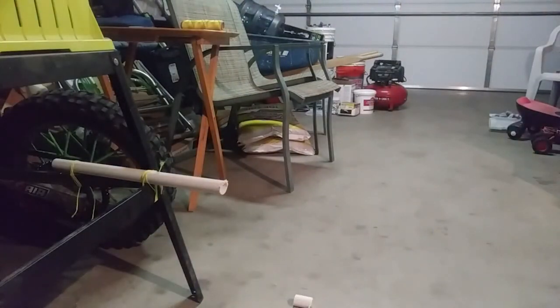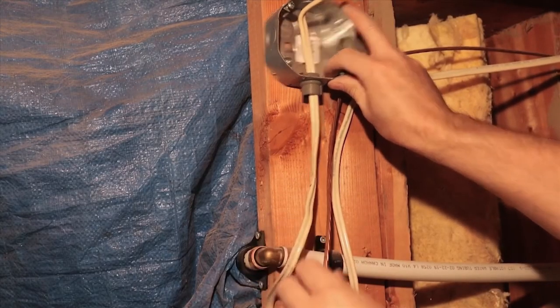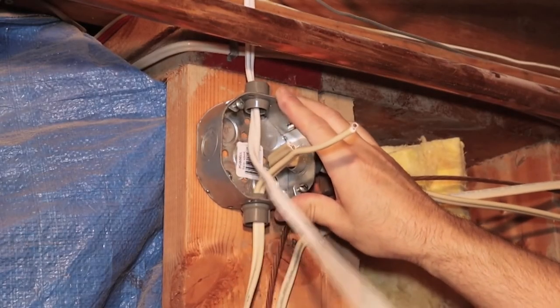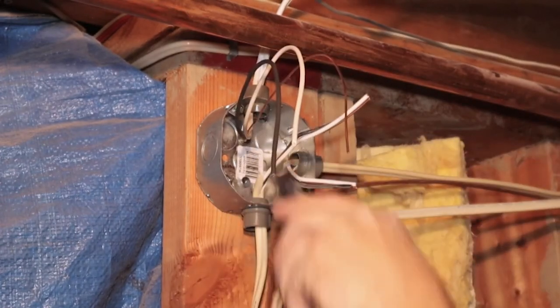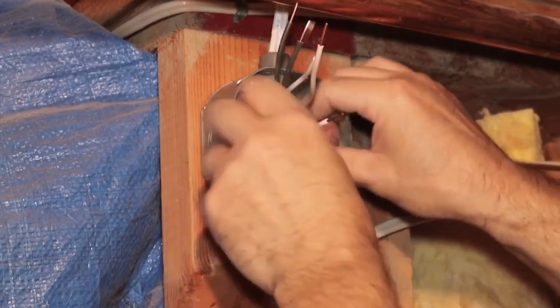Note: nylon string will not work because nylon and the PVC will melt together. Unsheathe before boxing. Contrary to popular practice, it is much harder to strip wires once they're inside the box. It may seem more efficient to push them through sheathed, but you're only setting yourself or another electrician up for trouble down the road. Always strip your cable sheathing before pushing them into the box knockouts. Measure carefully, because you will need at least a quarter inch of sheathing still in the box. And the most common piece of electrician advice: always leave yourself extra slack.